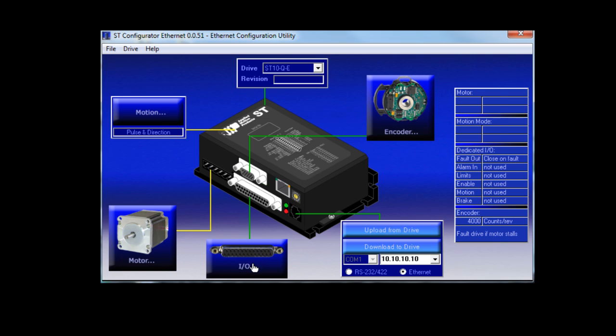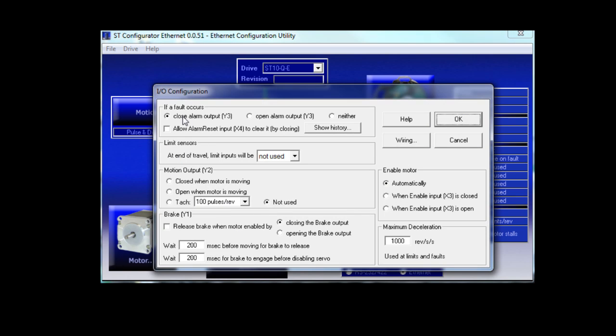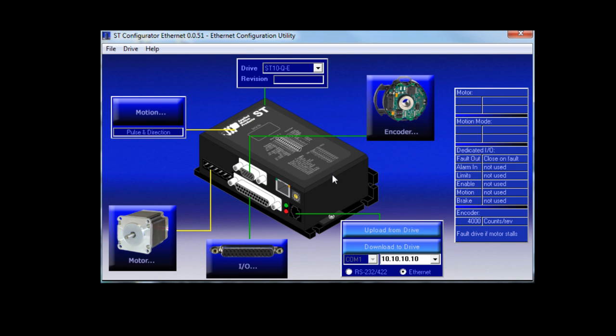Let's bring up the I/O settings now. I want to choose close alarm output if a fault occurs. That's output Y3 by default, which is what we've wired our LED to. Now we click download to send the settings to the drive.